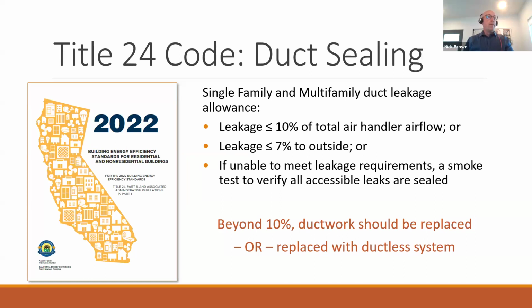So the duct leakage allowances: 10% of total air handler airflow, or 7% to outside, or a smoke test. That's what the code requires. But I think as a best practice, I'm here to say beyond 10%, let's replace our ductwork or replace it with a ductless system.